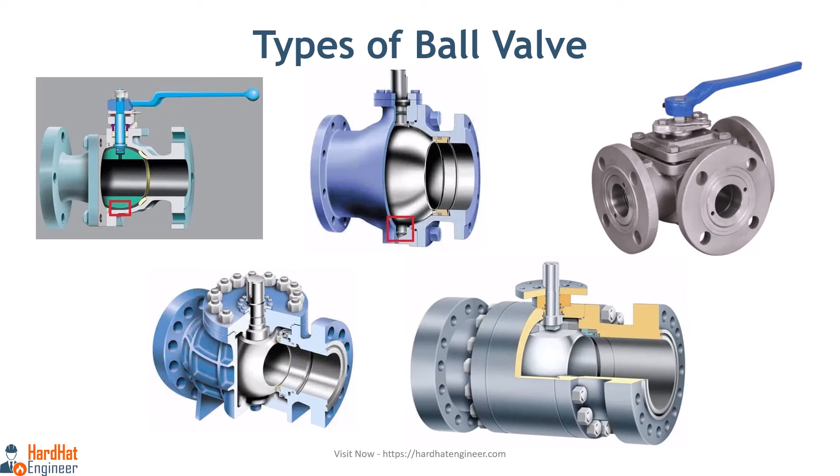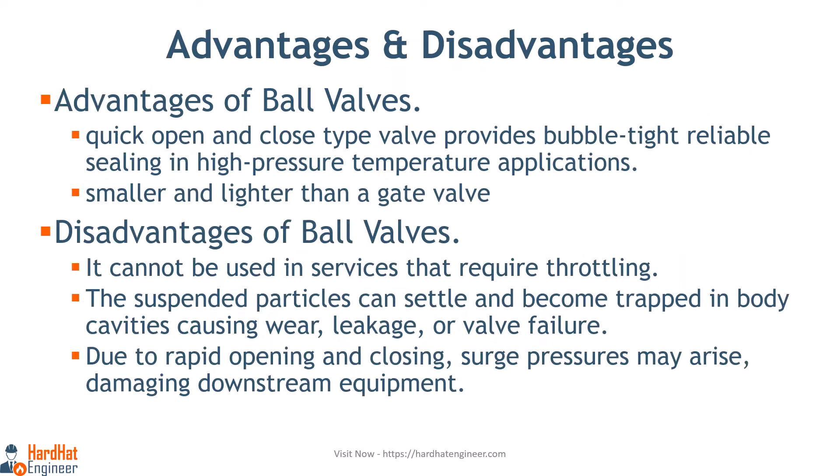There are different types of ball valves available, such as floating, trunnion-mounted, three-way, top entry, side entry or split body, and three-piece body design. The selection depends on the application. Advantages: it is a quick open and close, tight valve providing bubble-tight reliable sealing in high pressure and temperature applications. It is smaller and lighter than a gate valve of the same size and rating.